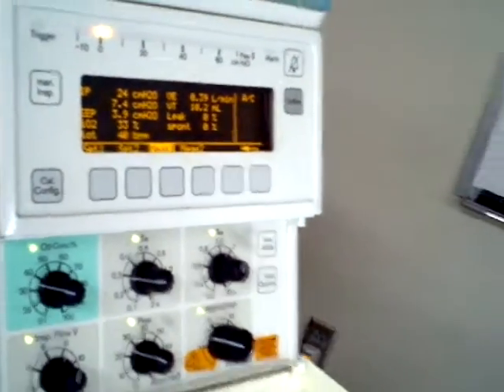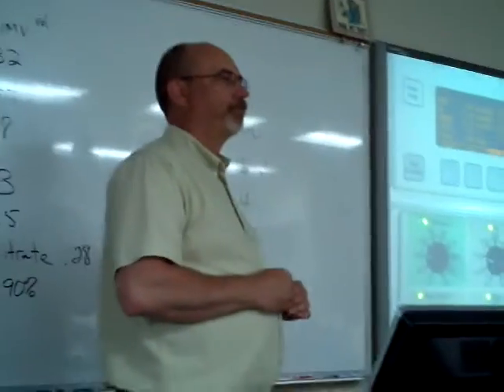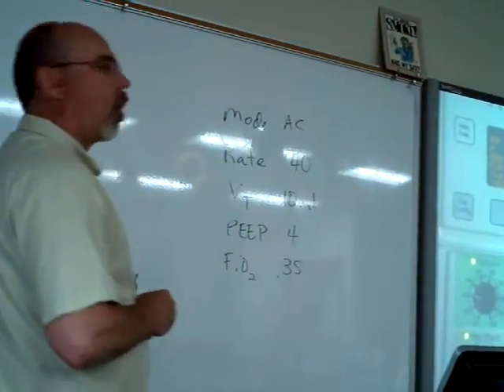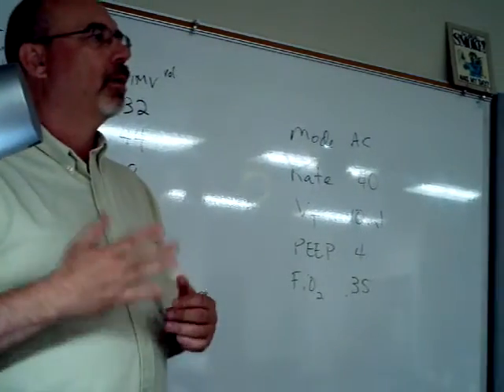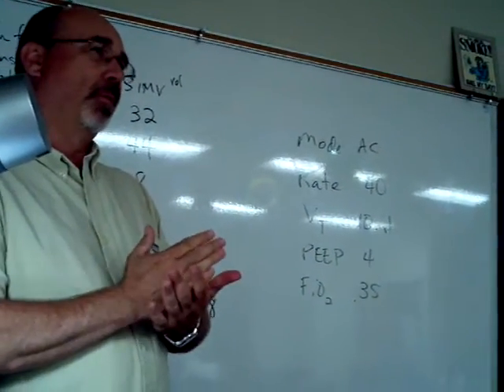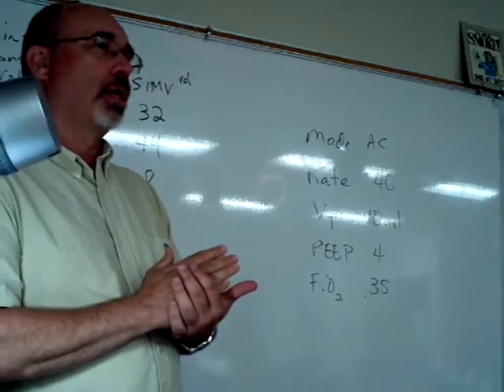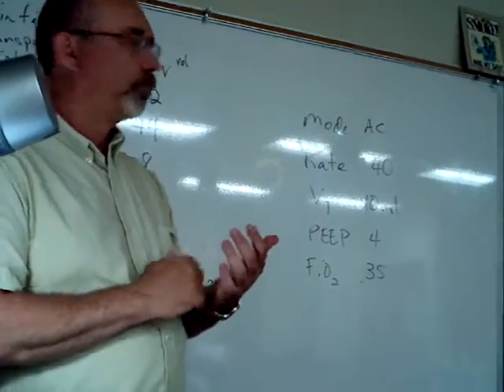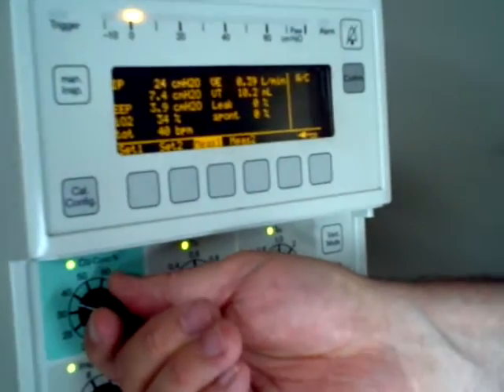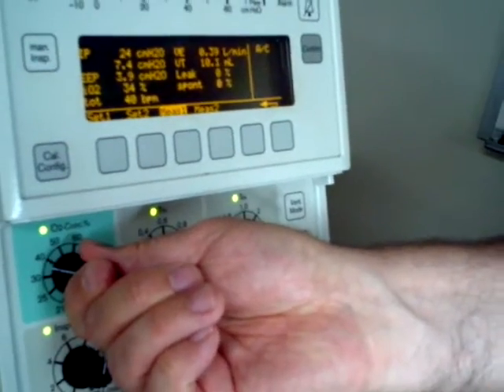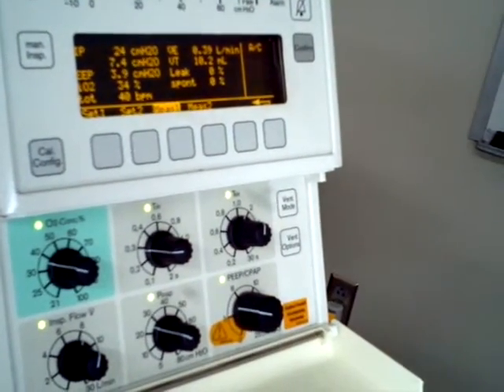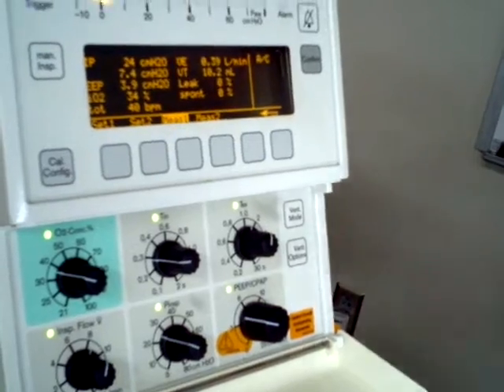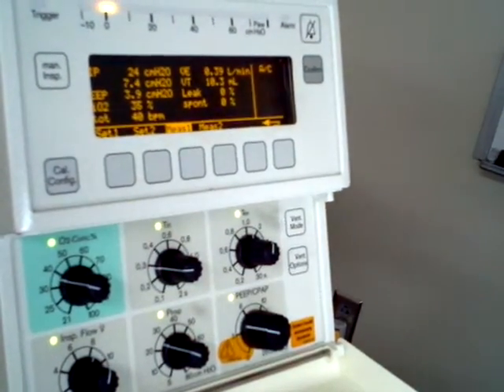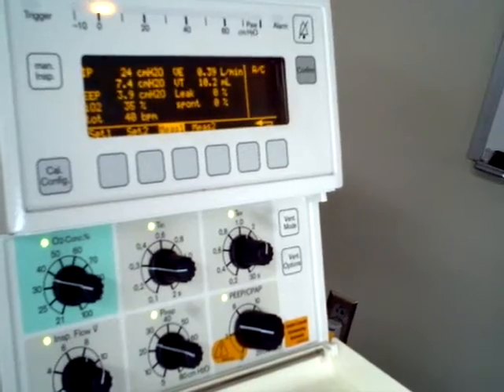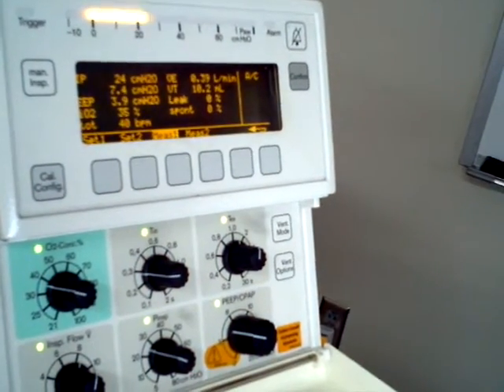That has, I think, to be a departmental protocol or rule, whatever you want to call it. Everybody should be doing the same. I would prefer to go by the measured oxygen percentage. So with that in mind, we'll do it. I'm going to turn this up to my measured. Keep in mind, most electrochemical analyzers are plus or minus 1 or 2% anyway in their accuracy. So if you're shooting for 35, you could hit 34, 36. Yeah. I mean, see, I'm bumping a little bit between 35, 36.